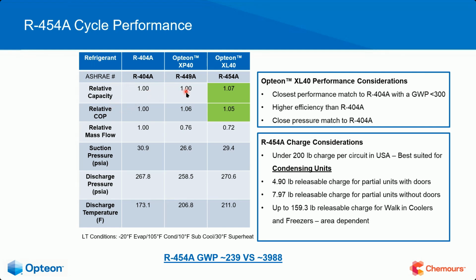Okay. When it comes to retrofitting 449A and capacity, you're losing nothing. It's equivalent. When we get the new equipment, the capacity is going to be 1.07 with 454A. All right. So you're actually gaining capacity on that. Let's look at relative COP. Again, relative 404A will be an example where we're comparing it to. That just means baseline or 100%. So it's 1.00 compared to 1.06 with 449A. And so you're actually gaining COP. And then on the new equipment, it's 1.05. So you're gaining COP on this.